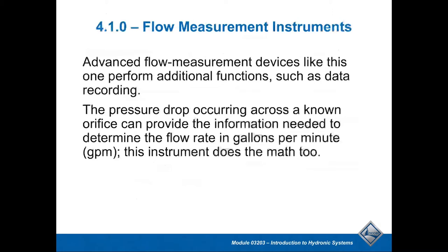Some of these devices obviously provide other functions and features. Nowadays they even make a kind of ultrasonic flow meter — devices that allow you to actually measure flow without having probes in the water. For example, at Lambeau Field, their mechanical systems have sensors on the water chillers that can actually measure the pulses of water as it flows through. They emit a signal through the water system and it determines water flow.